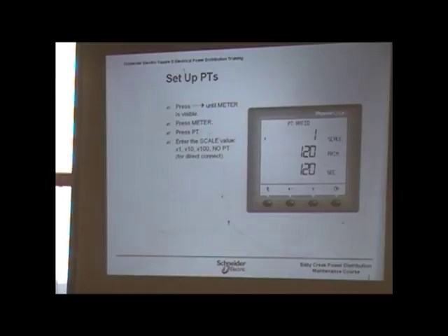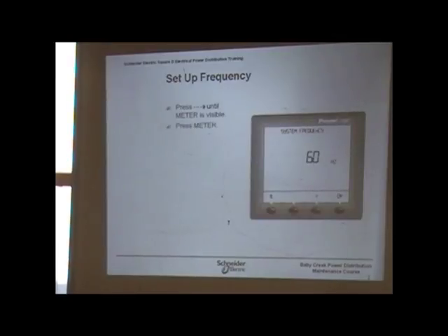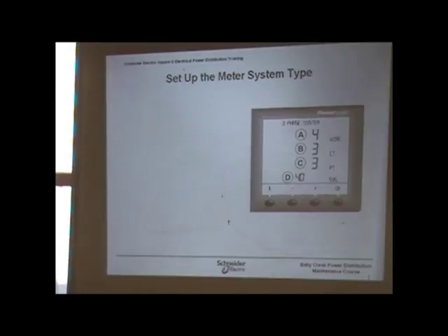PT ratio is basically the same thing, but the scale is 1 to 1 because the primary is 120 and the secondary is 120. So essentially, it's getting it directly from the line. The frequency is the same thing. Those are the three main things. More important is the CT. Meter type: a 3-phase, 4-wire system with 3 CTs and 3 PTs, they call that a 4-0 system.